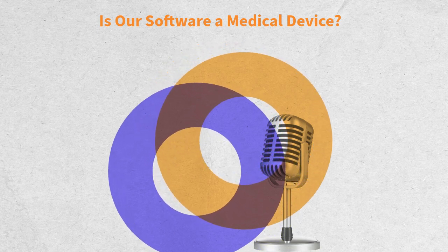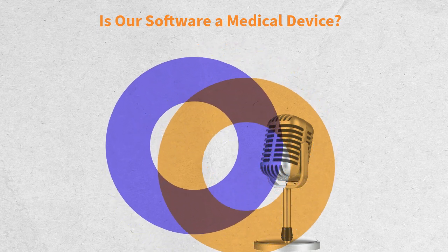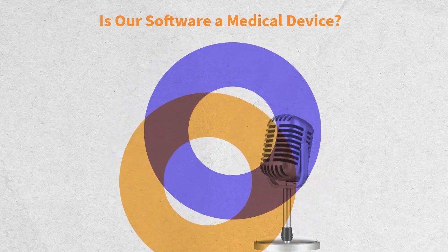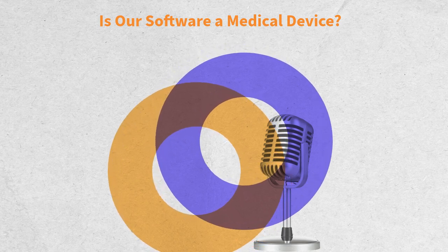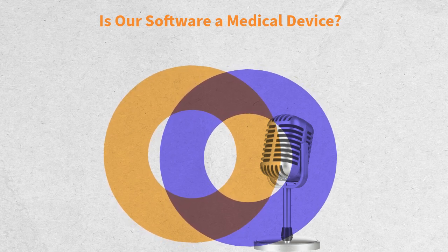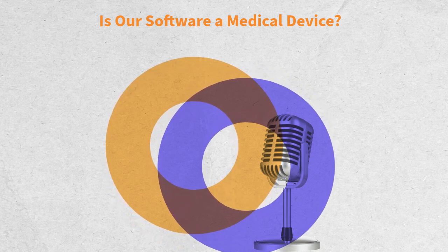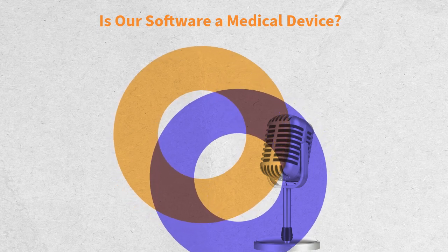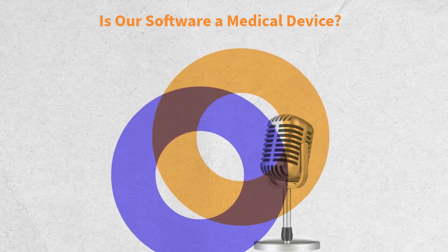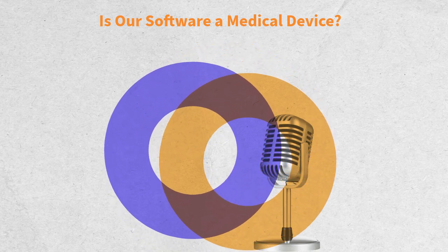An embedded software is an integral part of a physical medical device, such as an infusion pump firmware. They are both regulated by the MDR, but the classification may depend on the architecture and on the use context. A standalone software suggesting a diagnosis falls into Rule 11, the same for complex firmware inside the medical machinery.